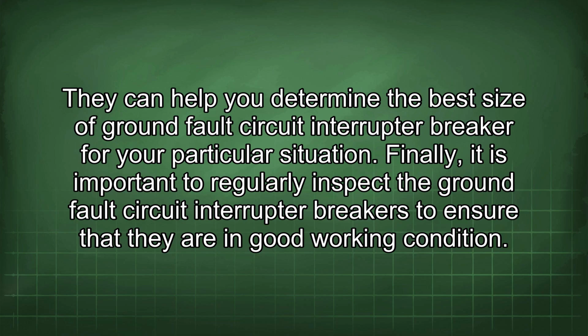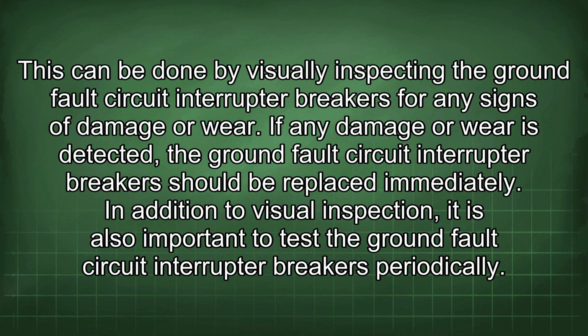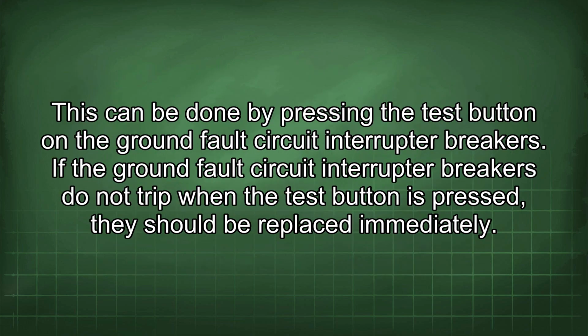Finally, it is important to regularly inspect the ground fault circuit interrupter breakers to ensure that they are in good working condition. This can be done by visually inspecting the ground fault circuit interrupter breakers for any signs of damage or wear. If any damage or wear is detected, the ground fault circuit interrupter breaker should be replaced immediately. In addition to visual inspection, it is also important to test the ground fault circuit interrupter breakers periodically. This can be done by pressing the test button on the ground fault circuit interrupter breakers.